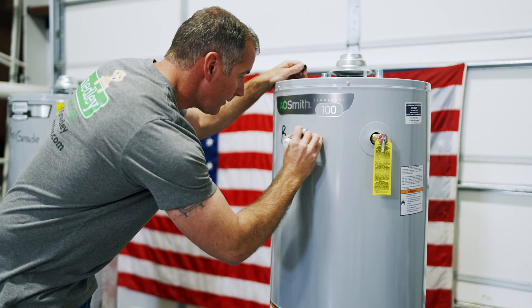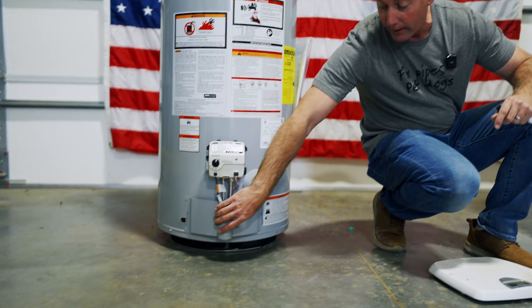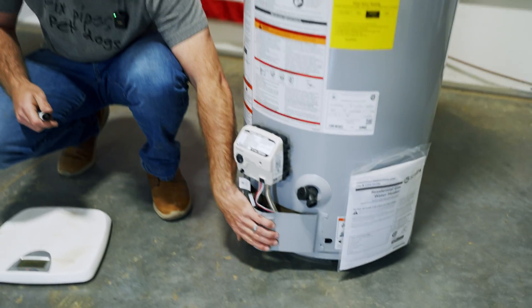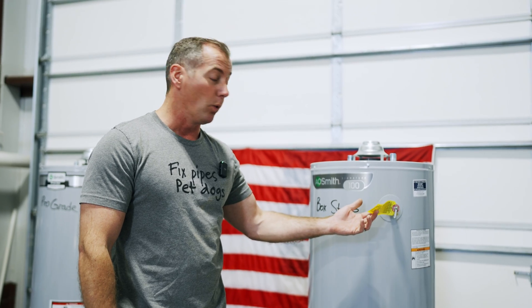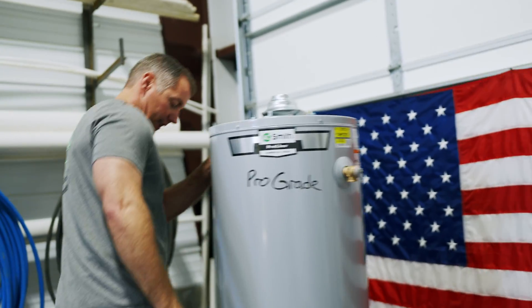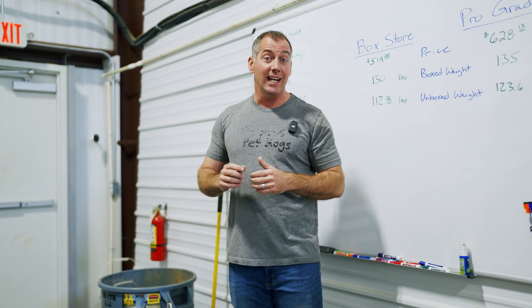Now that they're out of the box we can see some visual differences. The box store unit has a plastic drain valve; the pro grade has a metal drain valve. The door profiles differ — the box store one is fairly flat with a pronounced curve, while the pro grade comes away from the heater with a less pronounced but larger curve. The pro grade's temperature pressure relief valve has a warning tag and is substantially larger, and its nipples extend far enough to show flat pipe under the threads. Out of the box: box store unit weighs 112.8 pounds, pro grade 123.6 — a 10.8-pound difference.